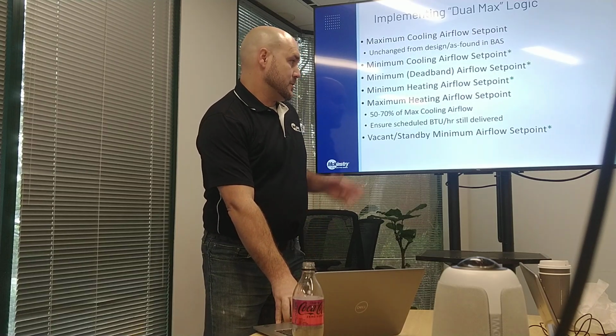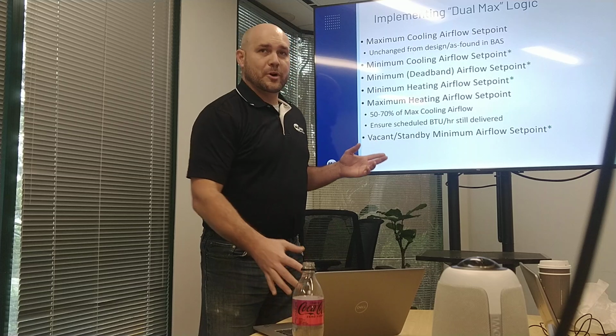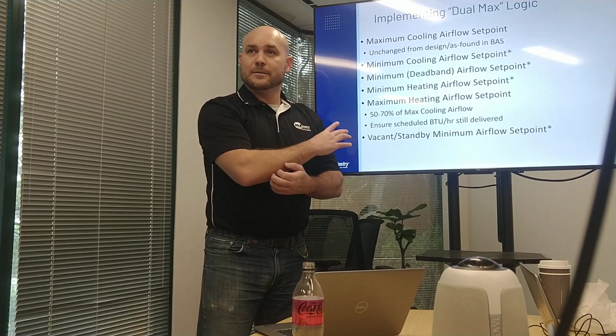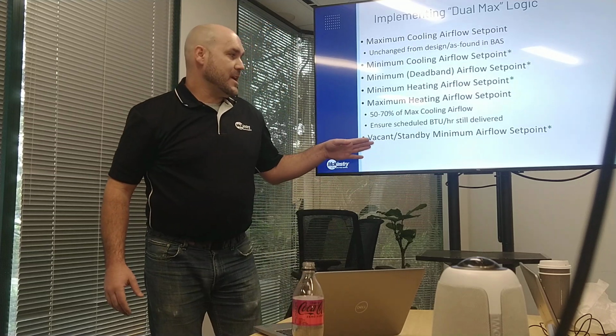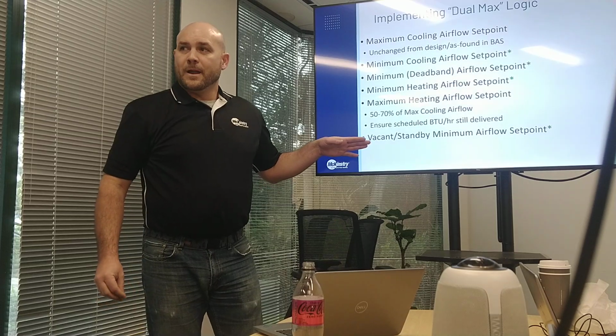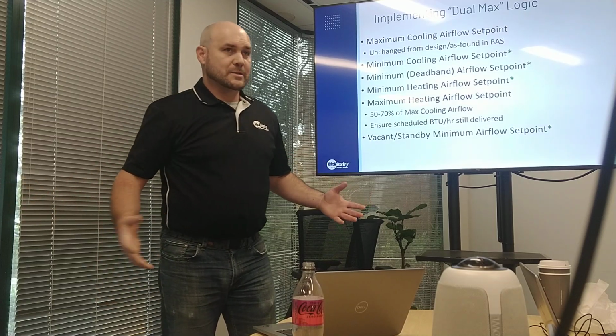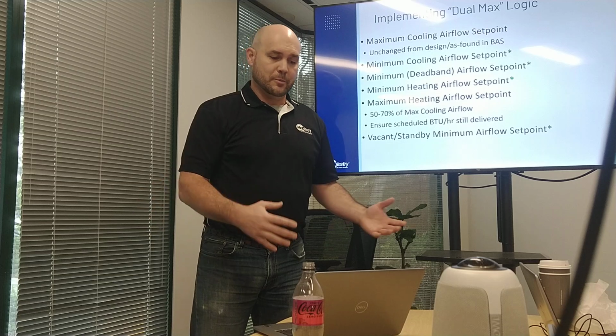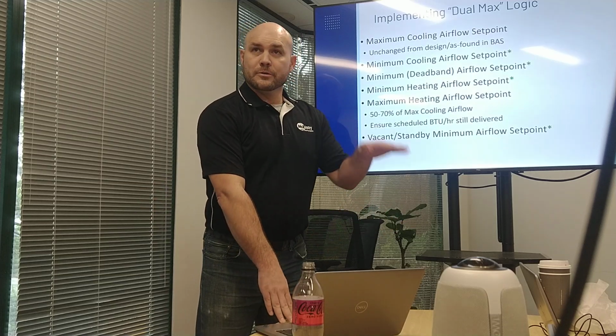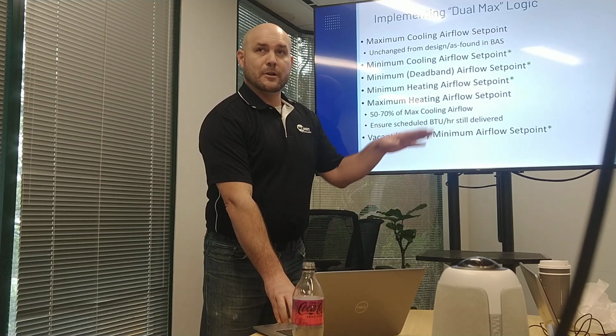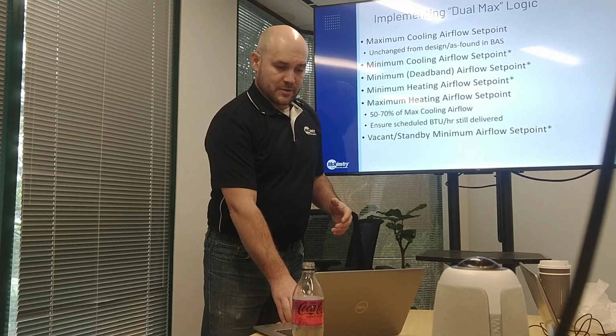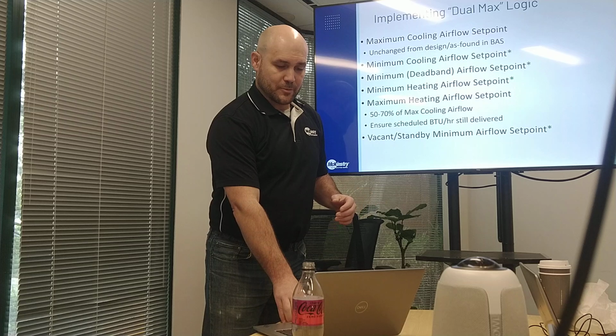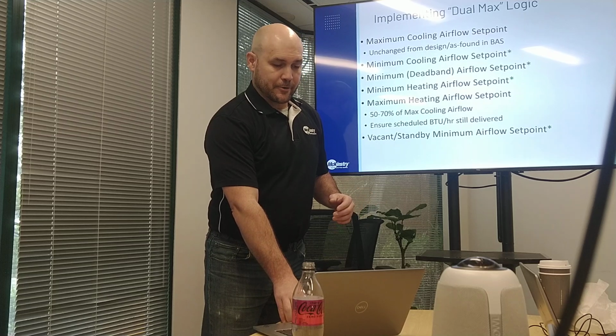Does that all make sense? So these green asterisks indicate, and certainly, there's this extra point that wasn't on the last slide, and that's a vacant or standby minimum when nobody's in the space. If the building's occupied but nobody's in the space, you can lower that minimum airflow even lower than what was on that graph. Those were all for an occupied space, but if you can determine that the space is vacant, all the better.